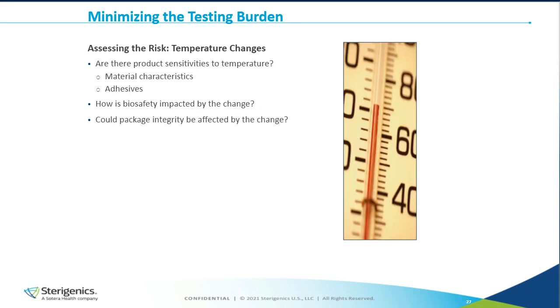The temperature change is, of course, one of the key drivers. The higher we can go, the better it's going to be for the cycle. But in terms of material characteristics and any adhesive that is being used in the device, we need to be cautious about elevation of temperature. So we need to find the best compromise that will leave the product functional without really impacting biosafety and without changing the integrity of the packaging, but still be efficient for the sterilization.